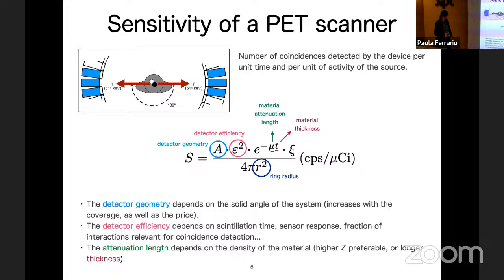There are several factors that contribute to the performance of a PET scanner. One is, of course, the geometry. So the longer your PET scanner, the better, because you detect more coincidences. So it is better a scanner of 2 meters instead of 70 centimeters. But of course, this comes at a price, which is basically the cost of the detector. Another thing is the detector efficiency, and it goes with the power of 2 because we have 2 detectors that have to detect 2 gammas in coincidence.